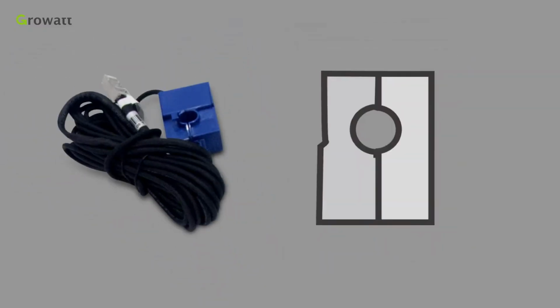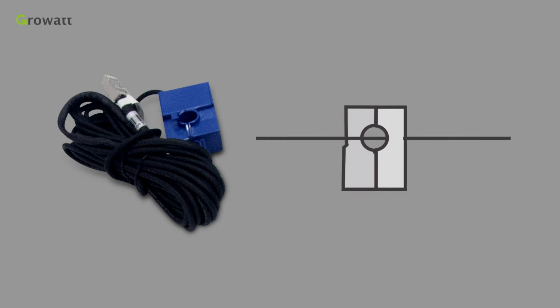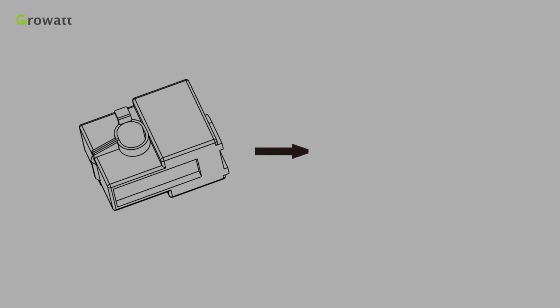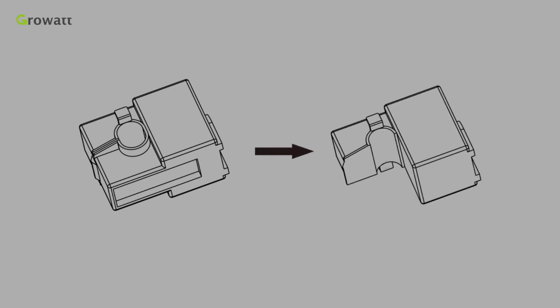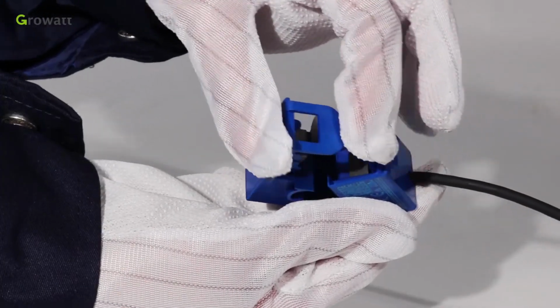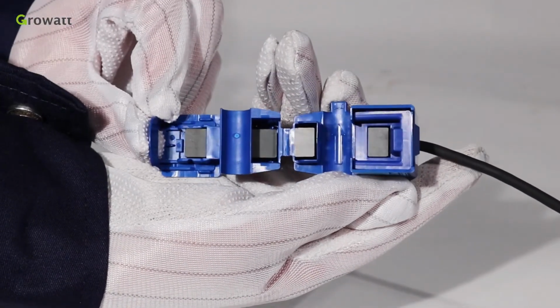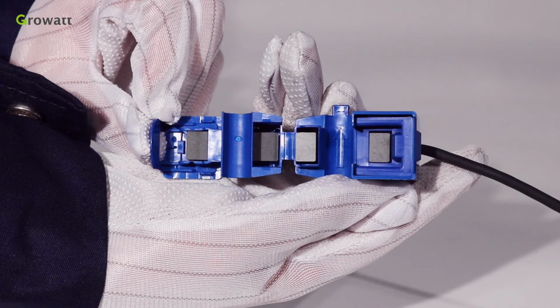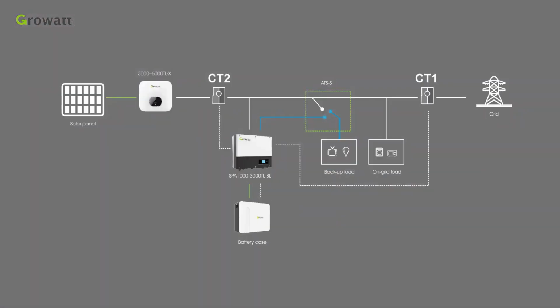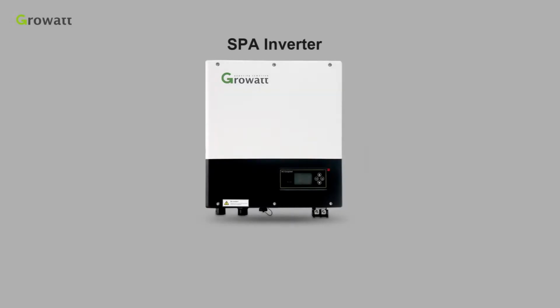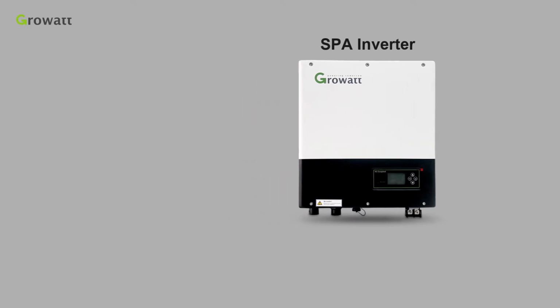Normally, we use 1 CT to measure the current through the live wire. One most important thing is to pay attention to the direction of the sensor. As illustrated below, open the current transformer and you can see an arrow labeled on it indicating the direction of current. The direction of the arrow of CT1 means from public grid to user load, and the direction of the arrow of CT2 means from public grid to inverter if the SPA and existing inverter are installed in combination.